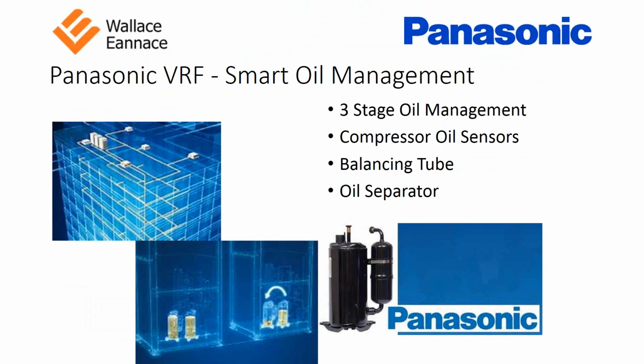So 3-stage oil management. Panasonic uses a 3-step process in order to retrieve oil. So what they do is they have a compressor oil sensor. They sense oil levels. When oil levels are low, they're able to go into forced recovery mode and retrieve oil from the indoor piping circuit and the indoor units to bring oil back to the compressor. They also use a balancing tube. So when our VRF condensers are linked together, we have a balancing tube that is basically an oil tube. So if one compressor and one condenser is low on oil, we can borrow oil from another condenser that we're connected to via the balancing tube. So it's basically a shared oil system with the balancing tube.